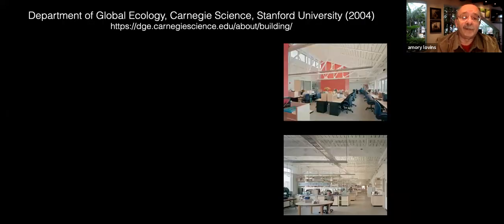Now, Stanford has the Carnegie Department of Global Ecology with a wet lab workshop and office that uses only 53% the usual amount of electricity compared with strict California code, and it emits 28% of the usual CO2, yet had normal construction cost, and it has exceptional occupant satisfaction. Except for under 200 hours a year, it's non-refrigeratively cooled and gets 50 units of cooling per unit of electricity. That's about 10 times normal refrigerative efficiencies. And it would have been not 50, but 100 times or more productive of cooling than it used electricity if Peter Rumsey had been allowed to design the pumping system too.